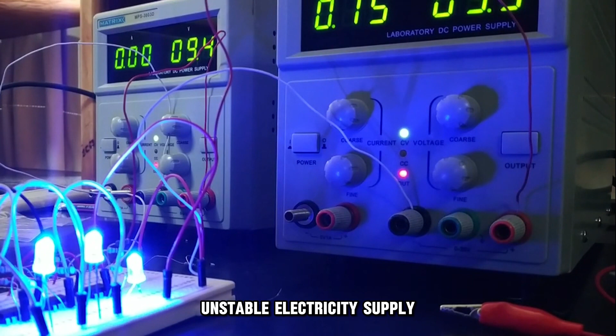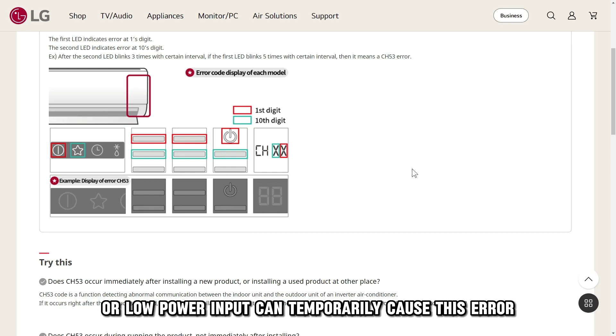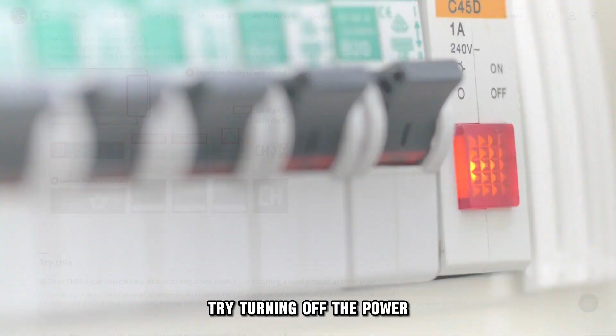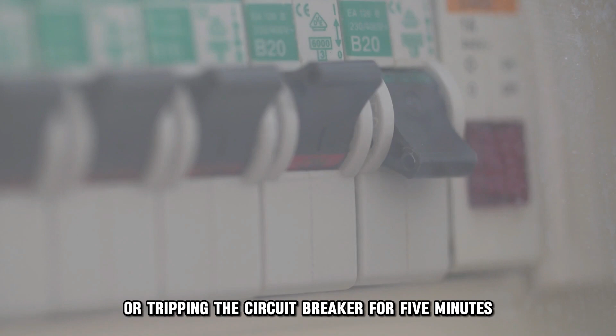Power reset the air conditioner. Unstable electricity supply or low power input can temporarily cause this error. Try turning off the power or tripping the circuit breaker for 5 minutes and resetting it. Also, ensure the outdoor and indoor units are operating at a power input of AC 230V.